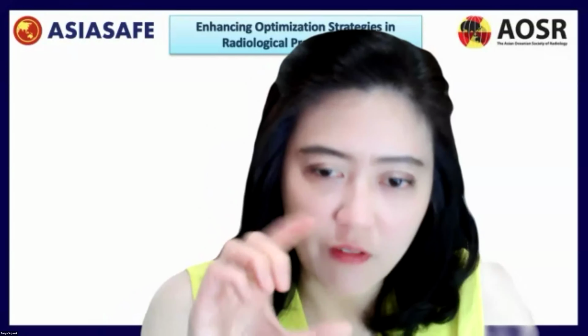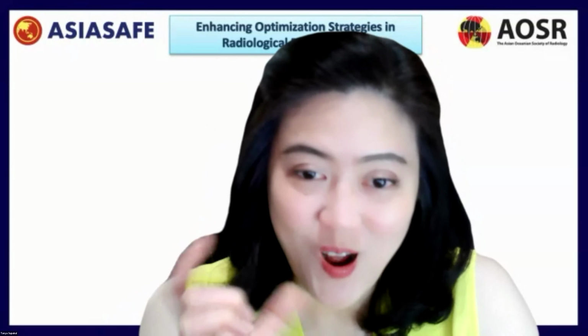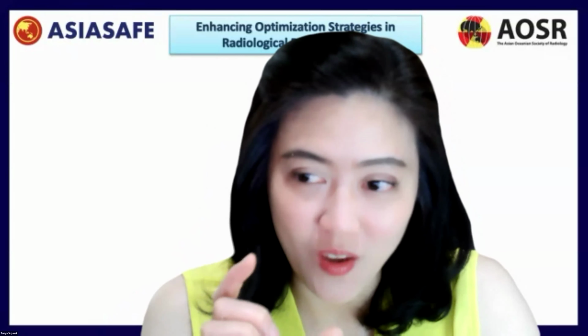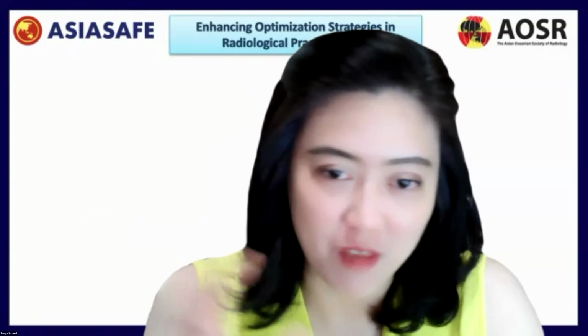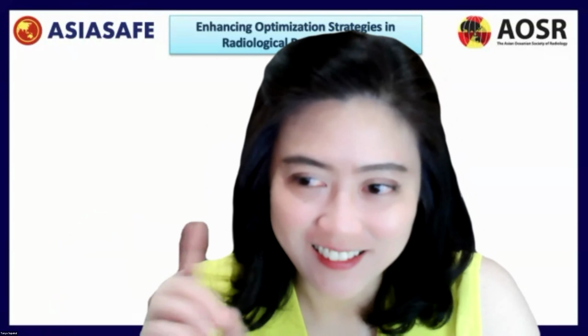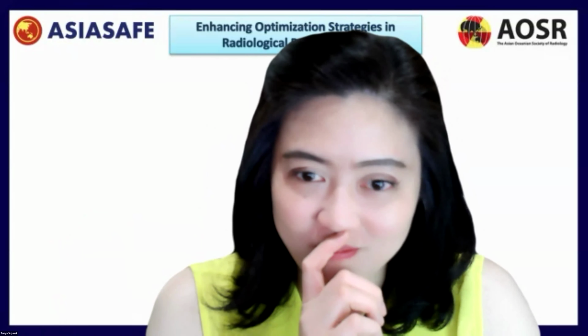Thank you. So 0 is a good number, but we have a range. If it's acceptable on the image quality, you might be okay. But if it's far beyond, maybe like a 5 or 10, that is something that we need to be concerned about.